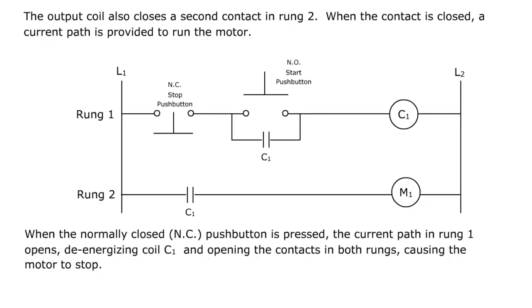When the normally closed pushbutton is pressed, the current path in rung 1 opens, de-energizing coil 1 and opening the contacts in both rungs, causing the motor to stop.